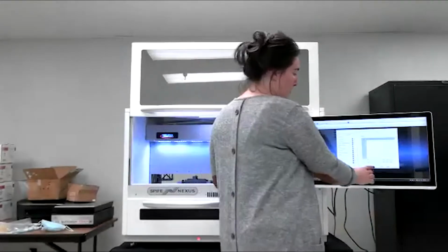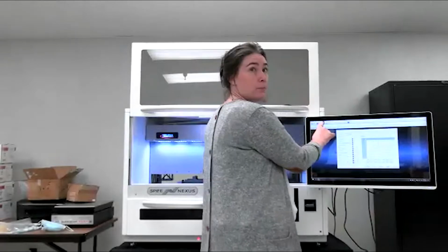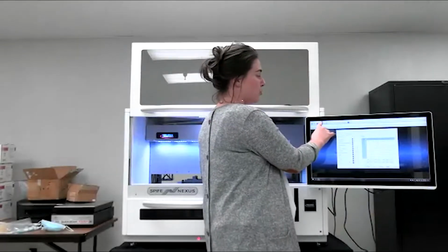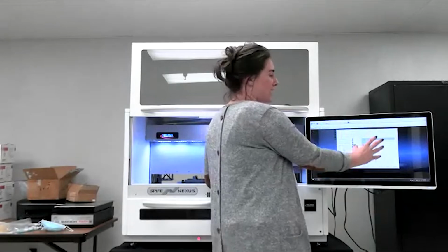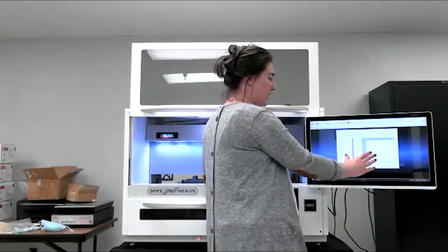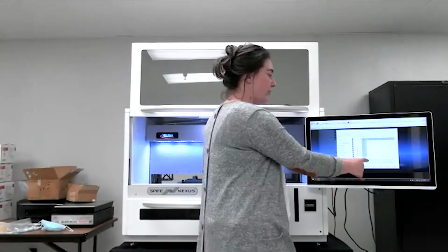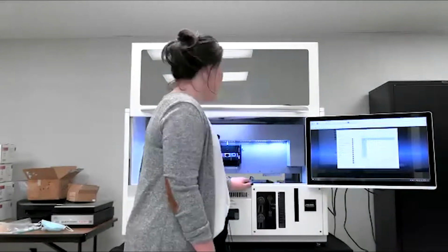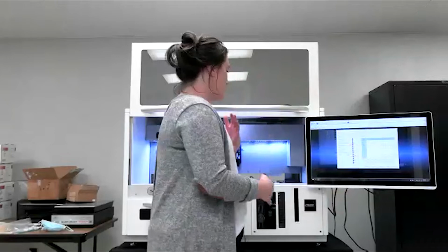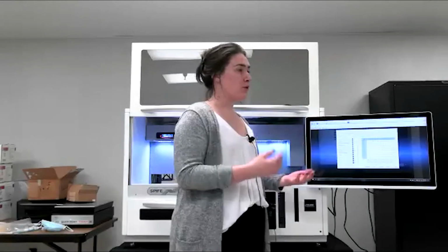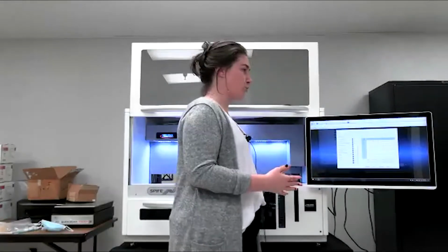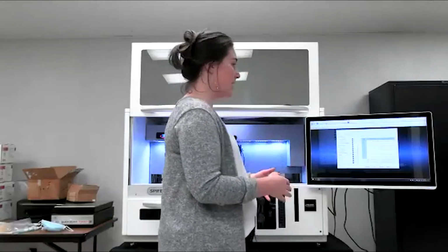So it's just to prime the machine. We have a prime button both at the top in this toolbar, and if you've already set up your run and have your dilutions as you like them, you can use the prime button within the start menu as well. And what the prime does is it pulls fluid through the system so that there are no air bubbles that could affect sample aspiration.